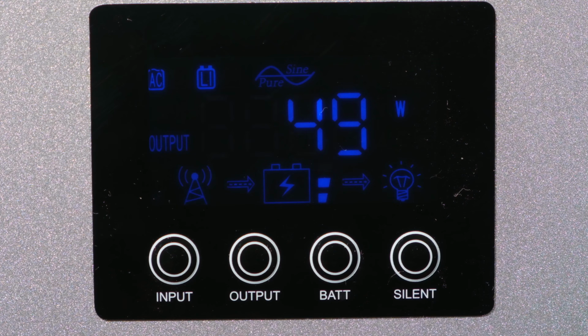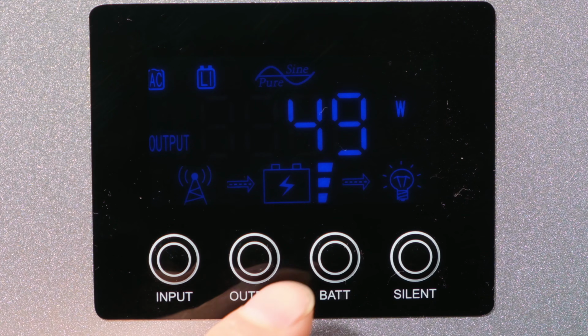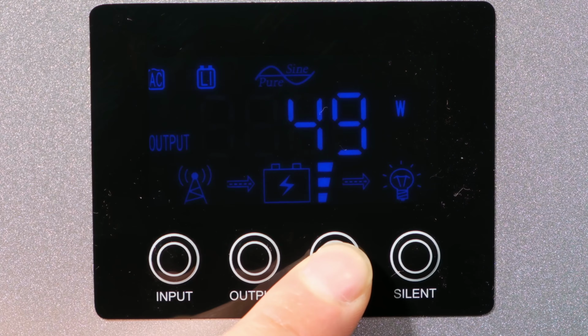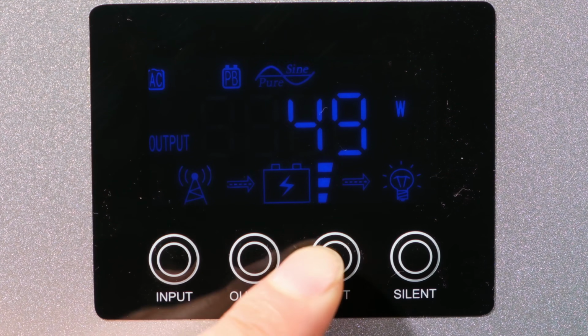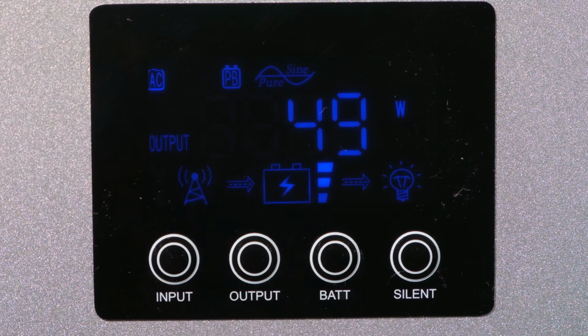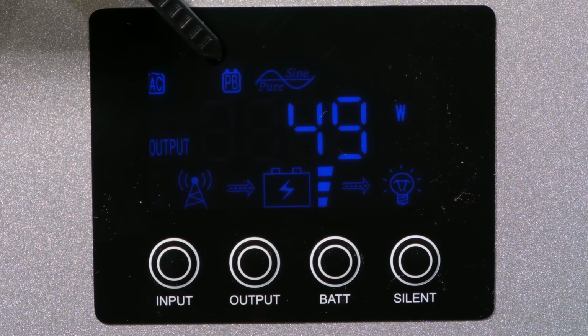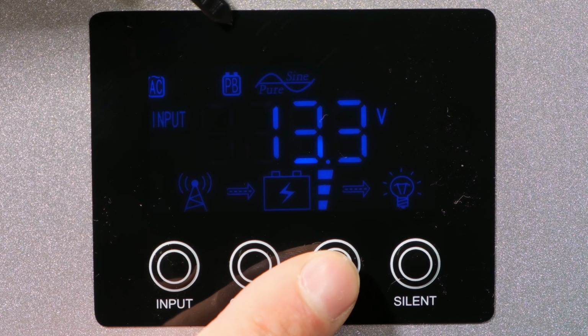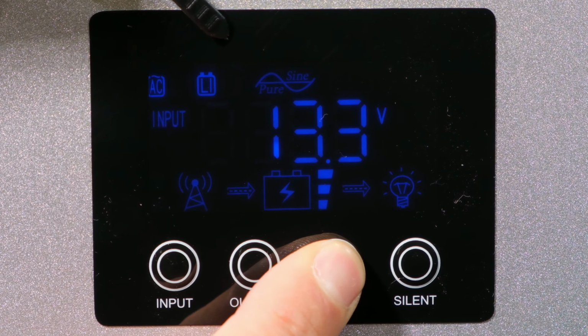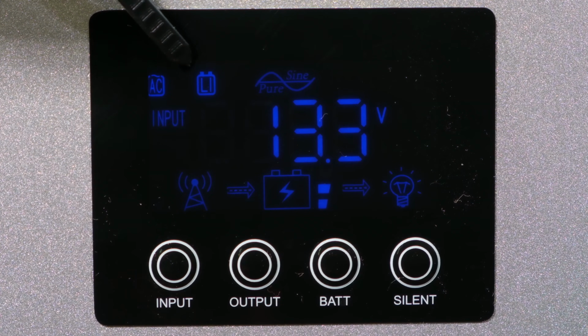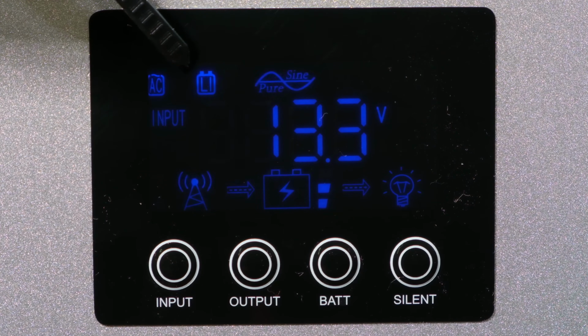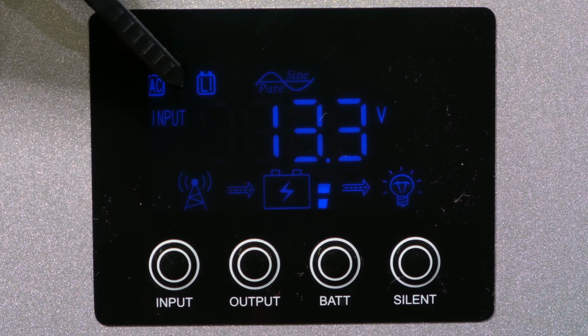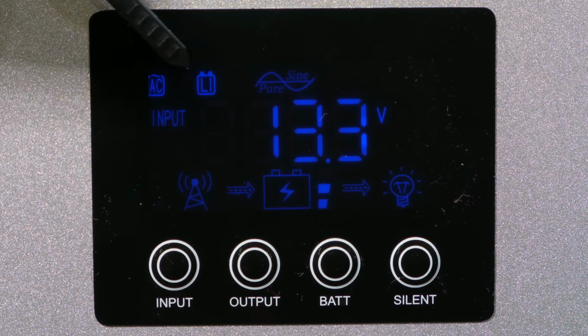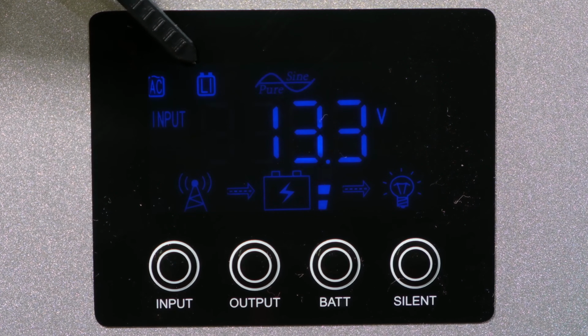If I do change the battery to a different type of battery, I can press and hold the battery there, and what it does is it changes it to a lead acid battery. So be very careful with that, because at the moment it thinks the battery is a lead acid battery just from pressing the battery for 1.5 seconds, and there it's immediately changed to the lithium. So just be aware that you are always in the correct profile. At this point I'm in the lithium profile because the battery is still lithium.